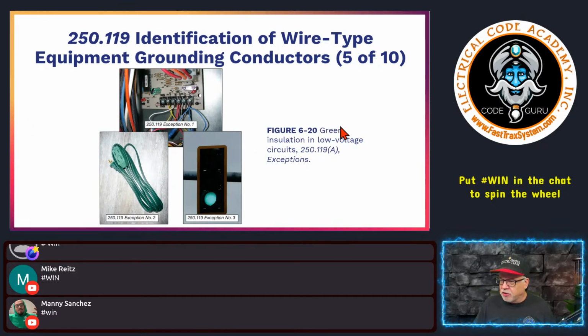So here we go right here. Green insulation in low voltage circuits, the exception. So here's that green cord, right? Remember, that's exception number 2, where it doesn't have one. Notice the prong doesn't have one, but the cord is green. So typically double insulated here, probably, right? Here is exception number 1, right here. Small circuits. I guess this is their under 50 volts AC or 60 volt DC application. So in these kinds of applications, it wouldn't matter. And then of course, this is your exception. And again, this is for traffic lights. I don't know how many of you do a traffic light, but again, you've got a little exception.